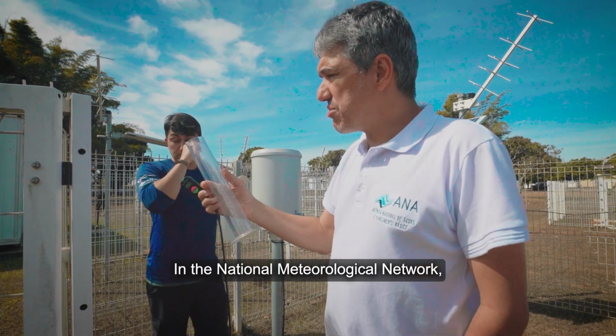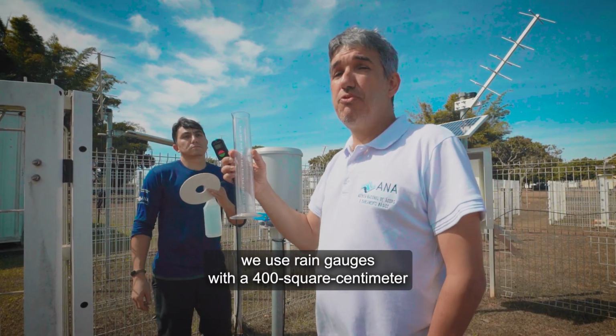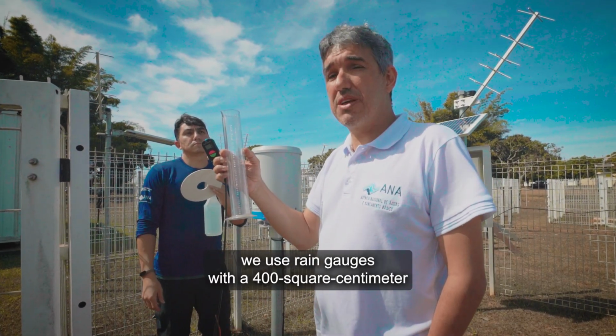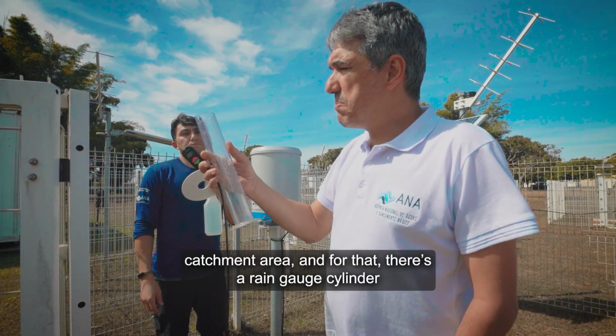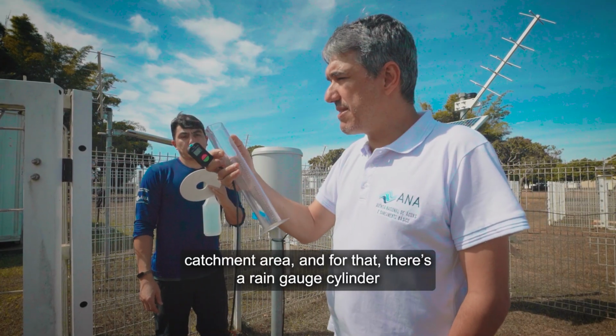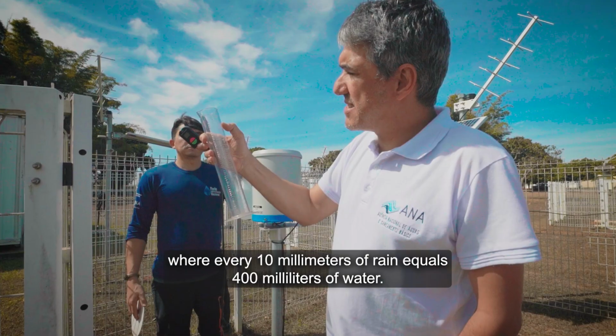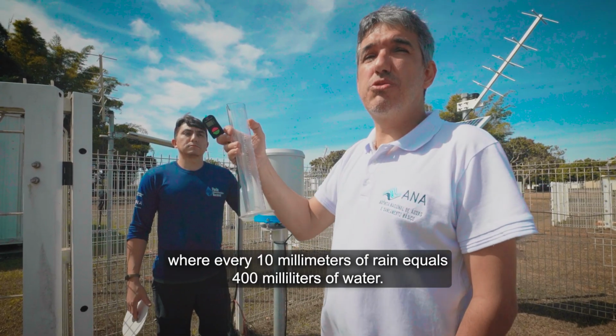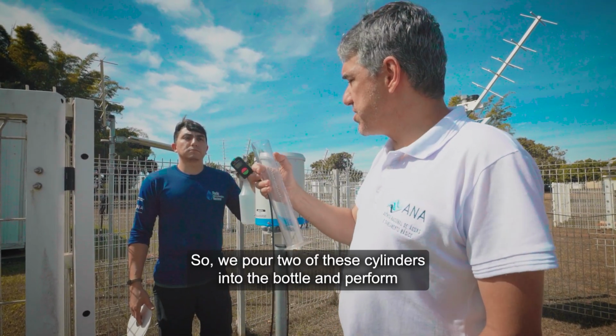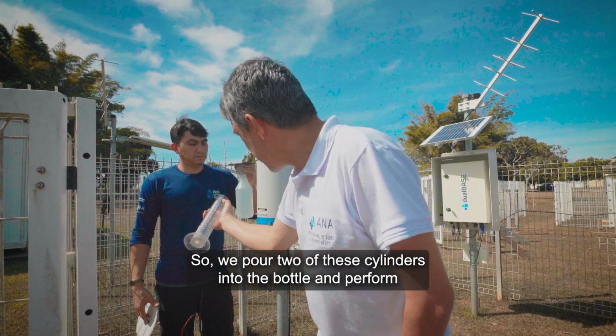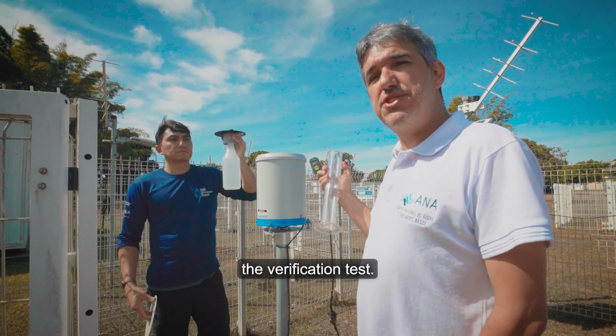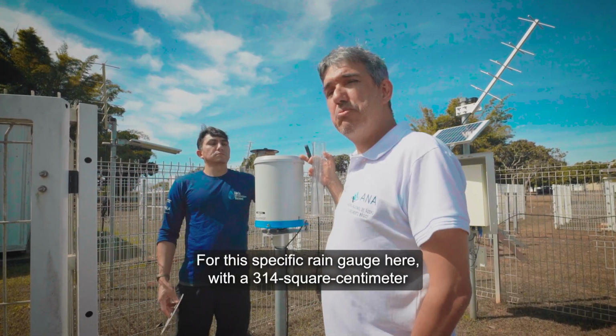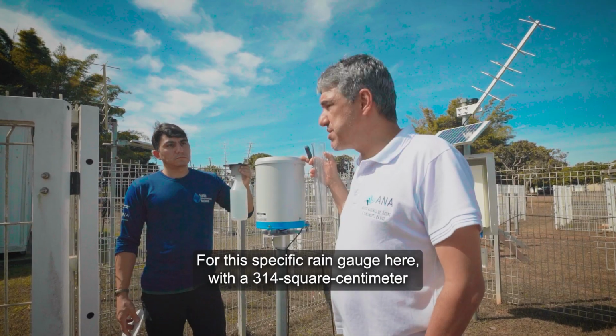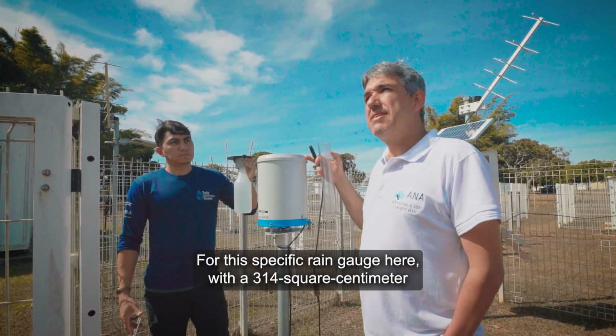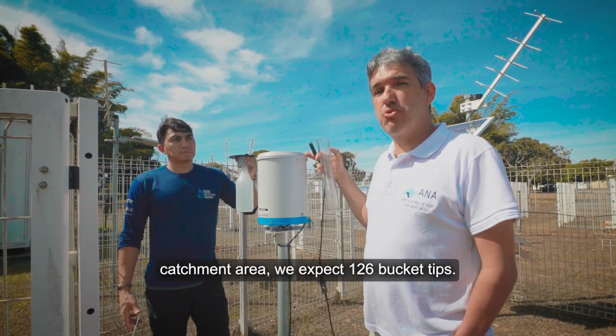In the National Meteorological Network, we use rain gauges with a 400 square centimeter catchment area, and for that, there's a rain gauge cylinder where every 10 millimeters of rain equals 400 milliliters of water. So we pour 2 of these cylinders into the bottle and perform the verification test. For this specific rain gauge here, with a 314 square centimeter catchment area, we expect 126 bucket tips.